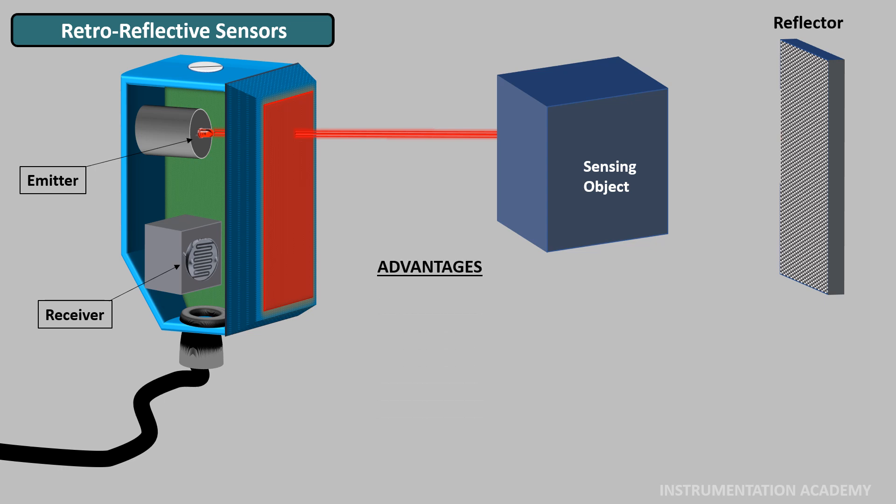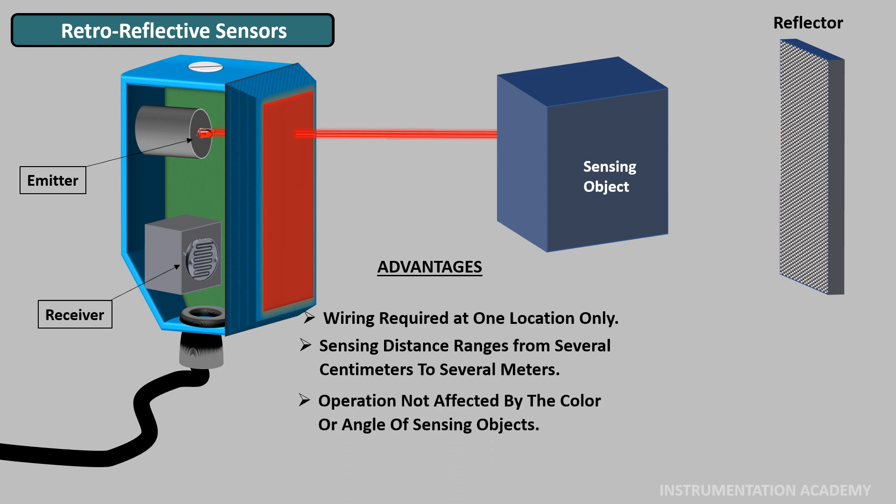Advantages of retro reflective sensors: As the emitter and receiver are on the same housing, one wiring location is only required. Sensing distance ranges from several centimeters to several meters. Operation not greatly affected by the color or angle of sensing objects. These are good for transparent large and reflective objects as well as objects moving quickly.